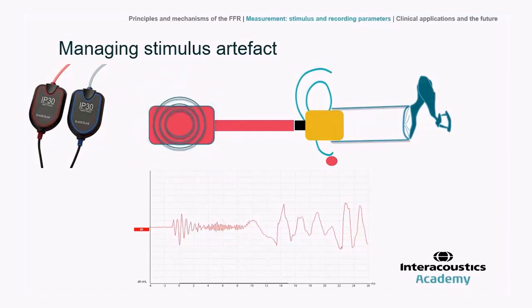So we can, of course, the distance is part of the way in which we manage that. The time delay allows us to present the stimulus prior to time point 0 on the latency axis. So we can see here this stimulus in the bottom panel starts at something like -1 or -0.9 milliseconds, and therefore that allows us to spot any stimulus artifact quite easily, because the response should be abnormally early in latency as compared with a true response, which should have happened downstream somewhat.